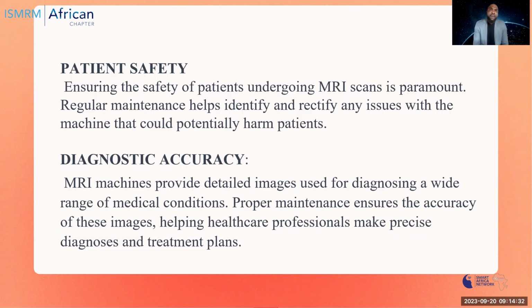Proper screening. MRI maintenance involves ensuring that safety measures such as the ferromagnetic object screening protocol are functioning correctly. Preventive maintenance includes verifying that the screening systems are optimal, ensuring that no ferromagnetic objects are present in the MRI room. Also, readiness for emergency situations is critical. In the event of an emergency, such as a patient experiencing a medical crisis during MRI, the ability to quickly and safely remove the patient from the machine is vital. Maintenance ensures that the emergency shutdown procedures are well maintained and functioning properly.